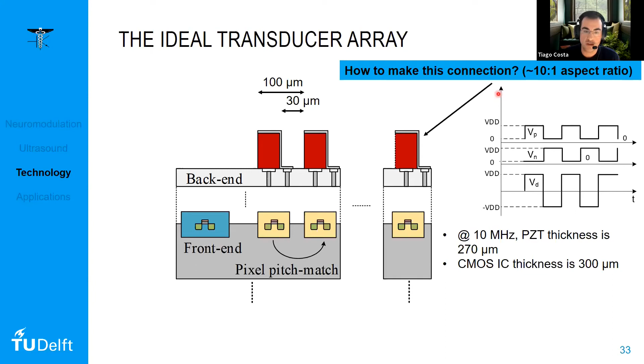Second, the silicon simulations have shown that it highly attenuates the output pressure. But we need the silicon because we need the CMOS chip. So how can we solve this? Maybe thinning the silicon and replacing it by a better material. And also a matching layer. PZT or piezoelectric ceramics are highly mismatched acoustically with tissue, meaning there's a lot of reflections. A matching layer can be fabricated on top to try to mitigate these reflections, but so far it hasn't been done, at least with good levels of transmission coefficient. So these are all fabrication challenges that need to be solved.